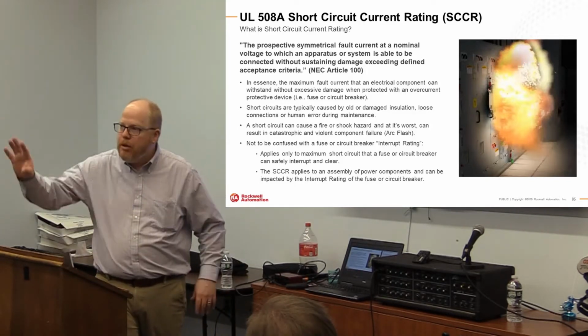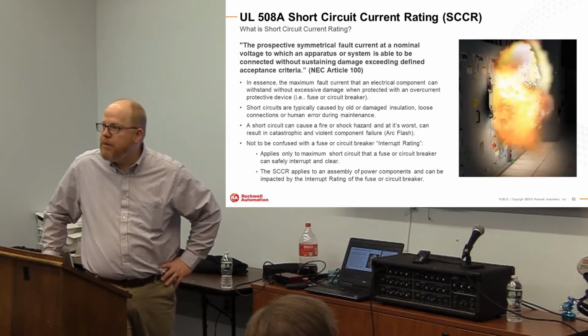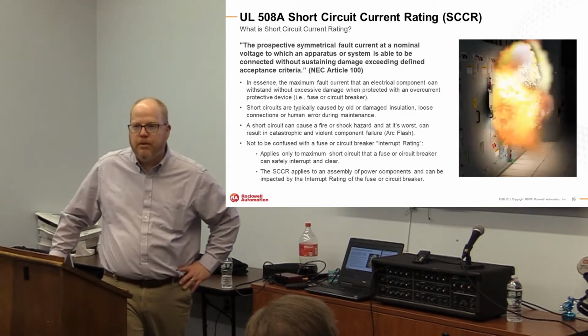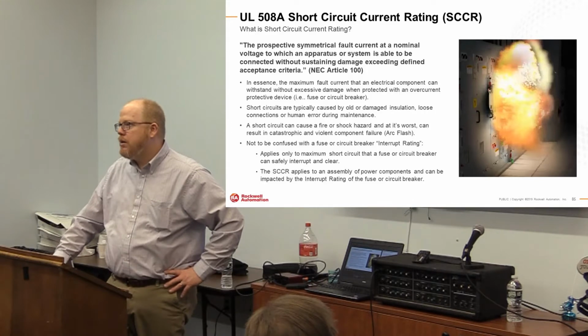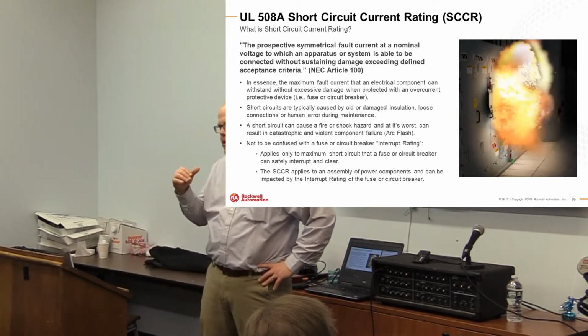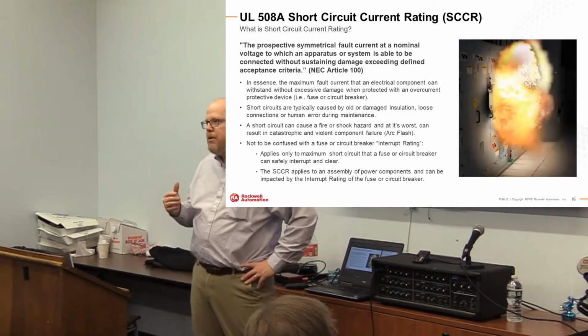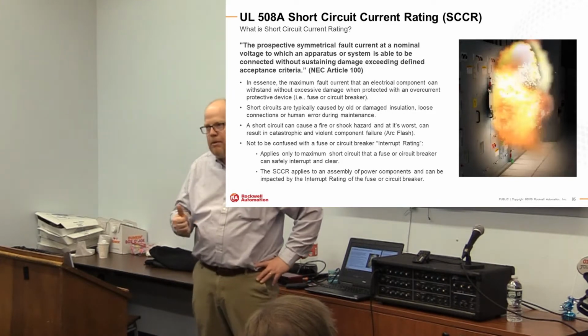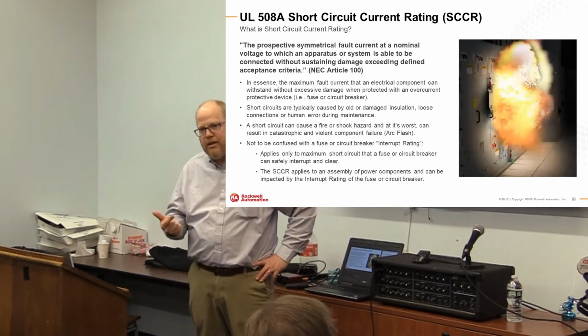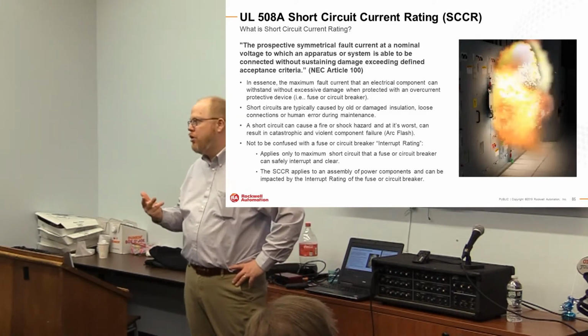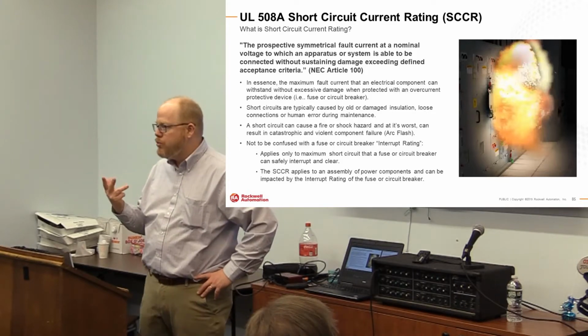But what I want to clear up is that bottom line: it's not to be confused with the breaker's interrupt rating. Now I'm going to start this next series of sections throwing out some jargon. I'm going to be throwing out short circuit current ratings, interrupt ratings, and we're going to talk about let-through currents. So we have to be real clear on the terms we're using here.